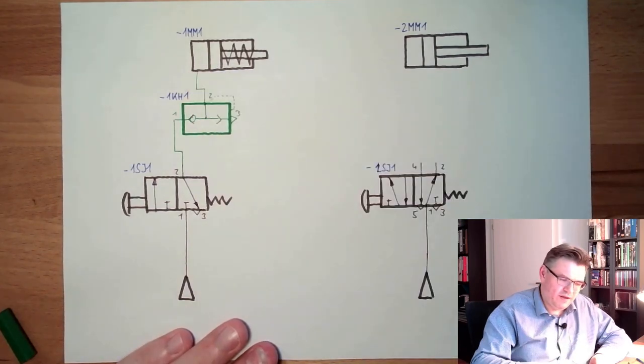So this means the distance between cylinder and quick exhaust valve should be rather small. Should be rather small. Here we have a cage. And so this is either directly at the cylinder or maybe a short hose or something like this.